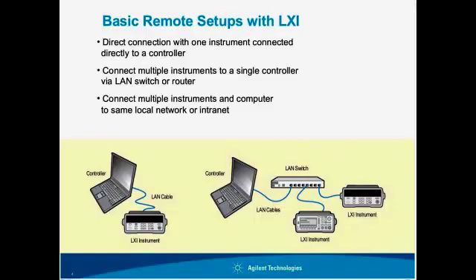A router can do something very similar, but a router does more. A router is a network device that can replace the LAN switch in the setup. The router actually creates its own local network and abstracts the instruments and your controller from any other networks you connect that router to. The router's network could be private, or connected to another network — the other network sees the router as its own individual IP address, and the router abstracts the instruments from the rest of the network.